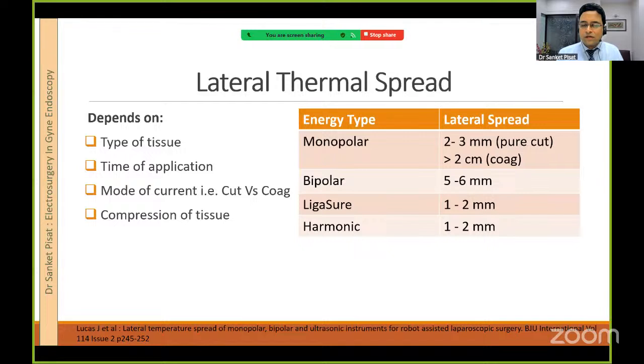In fact, now in robotic surgery, you will see extensive use of monopolar current, because if you use pure cut, the lateral spread is minimal. But if you switch to coag, the lateral spread can be as much as 2 centimeters. For bipolar, for most applications, it is 5 to 6 millimeters, and for LigaSure and Harmonic, 1 to 2 millimeters, but again subject to the variables mentioned on the left hand side.